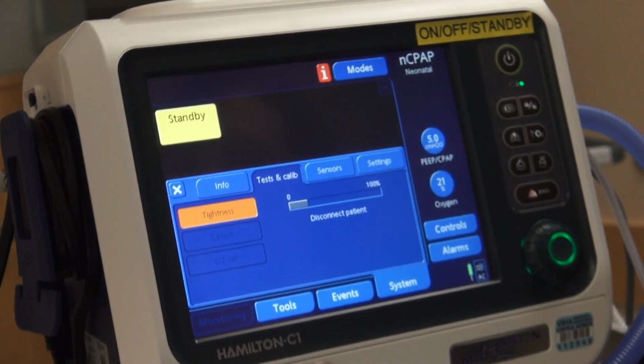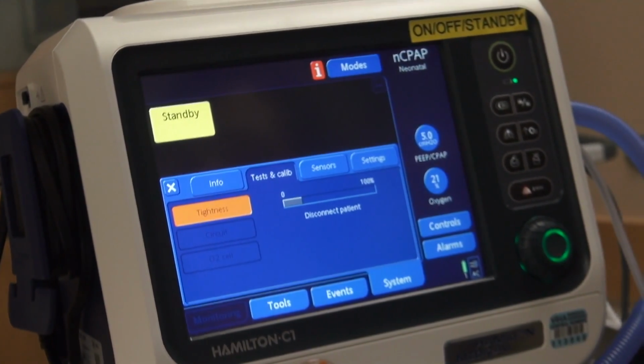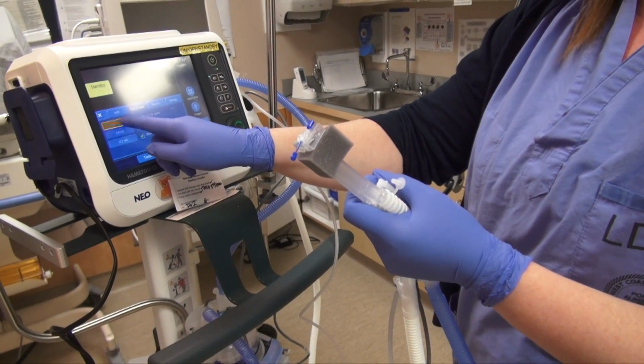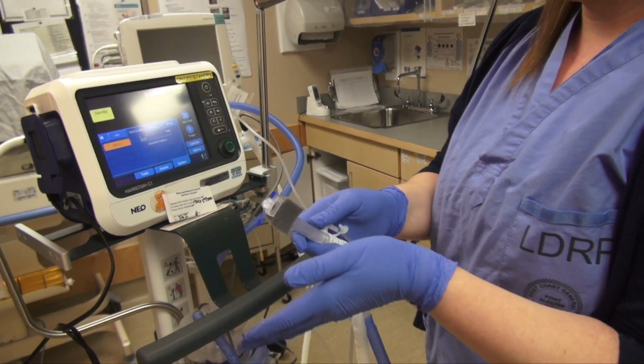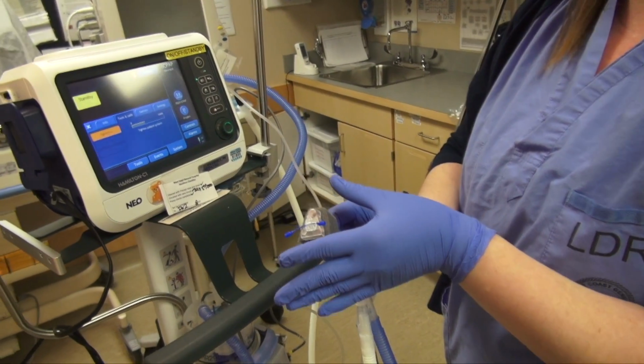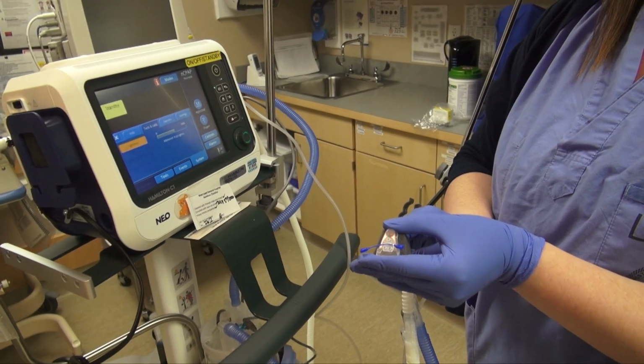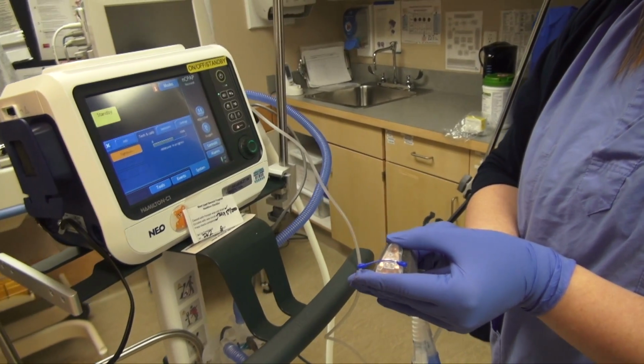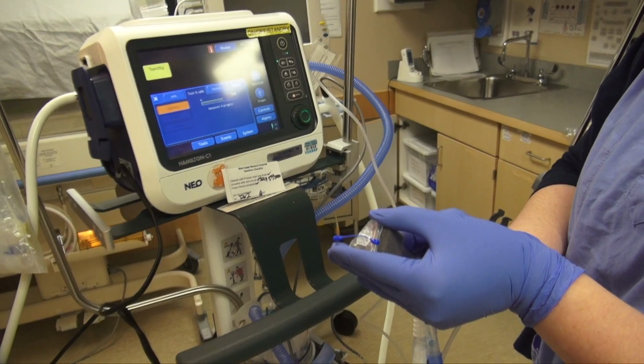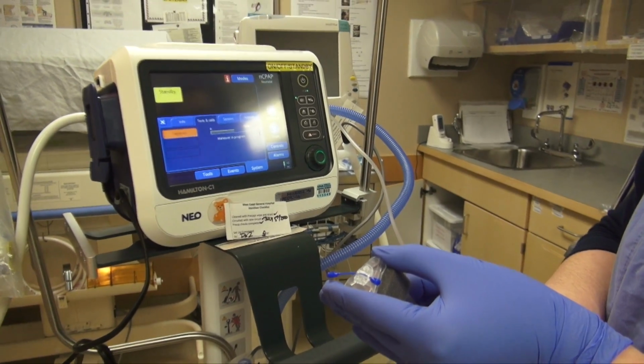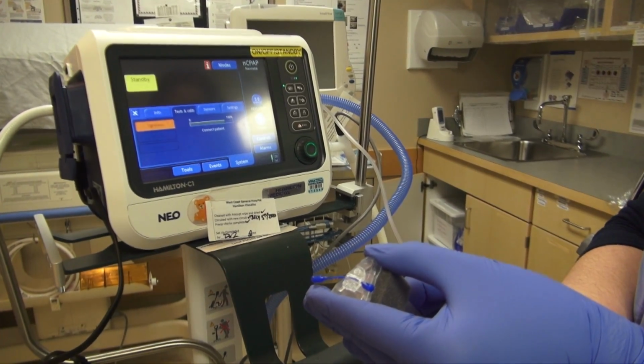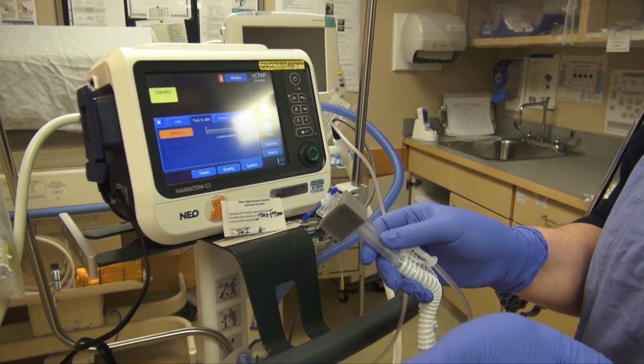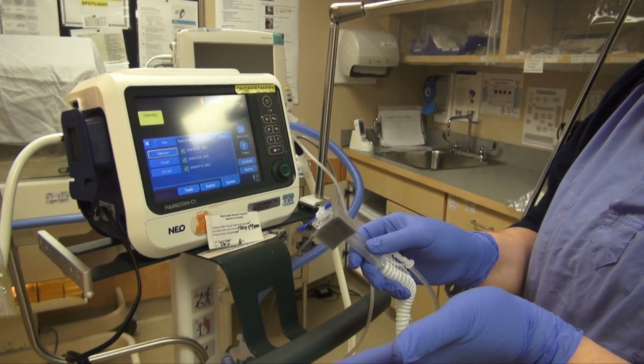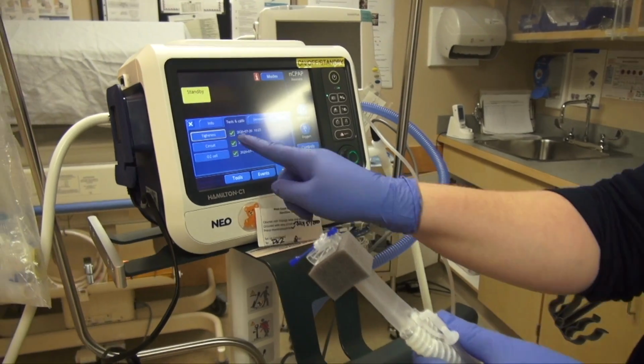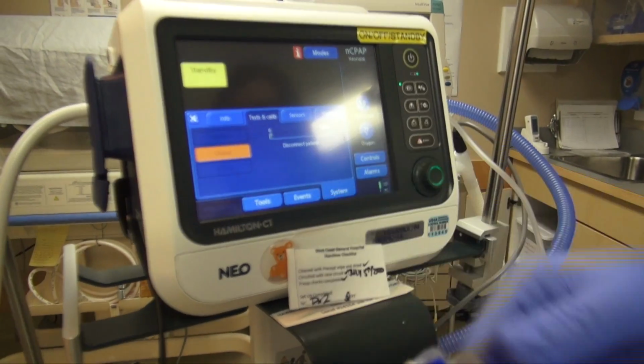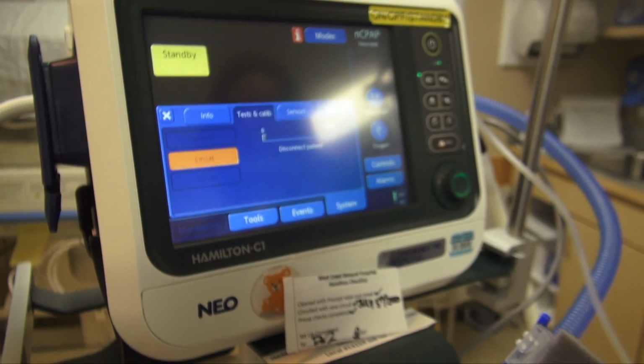Step 1, tightness test. This is to ensure the circuit is set up correctly. Touch the tightness button to perform the tightness test. Follow the prompts. Occlude end of the breathing circuit with a gloved hand when it says disconnect patient. Hold against your hand for the maneuver in process. Release when it says connect. Once complete, you should see a green check. If you get a green check, proceed to circuit check.